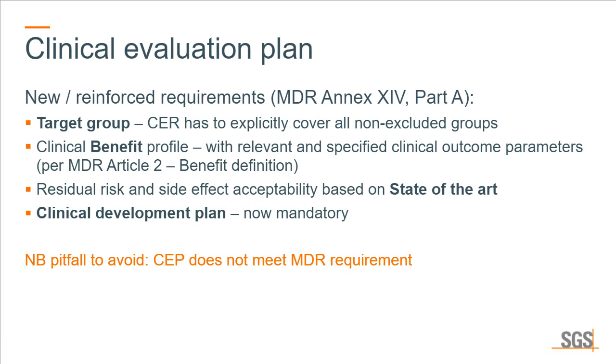considering that it's either using this device or nothing, but you have to look at the utility and the safety and the effectiveness of your device in the context of the whole world, basically, whatever is relevant. So it might be a competitor's medical device, but state-of-the-art also includes all those different methods in the world that can reach the same clinical benefit as your device. So it can be a lifestyle change. It can be pharmaceutical use instead of medical device use. It can be your competitor's medical device use. So you have to consider this as well.